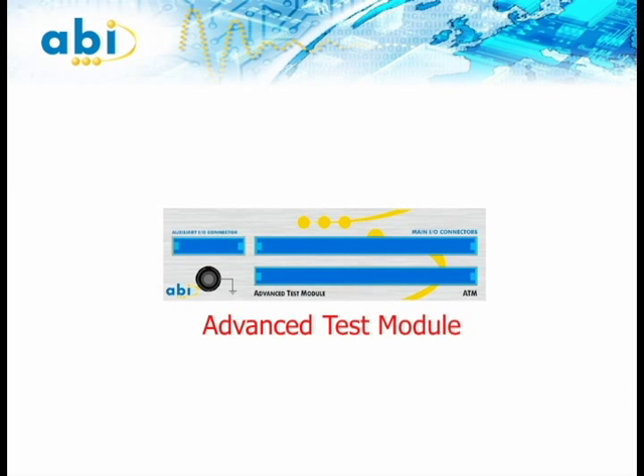The second module is the Advanced Test Module. The ATM is a solution designed for the test and diagnostics of all digital ICs and PCBs from all logic families including TTL, CMOS, and ECL. The module offers power-on and power-off tests either in or out of circuit. With high specifications and up to 2048 channels, the module is ideal for both component and board level testing.